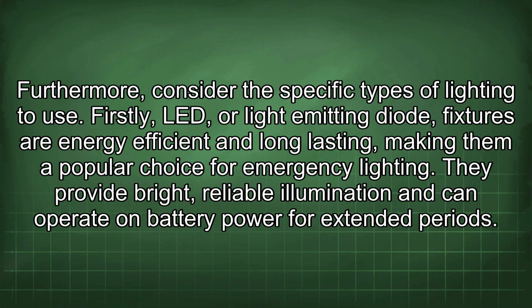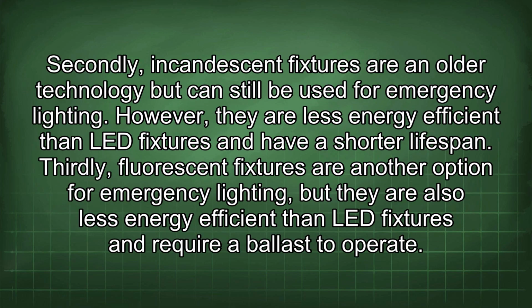Furthermore, consider the specific types of lighting to use. Firstly, LED, or light-emitting diode, fixtures are energy efficient and long-lasting, making them a popular choice for emergency lighting. They provide bright, reliable illumination and can operate on battery power for extended periods. Secondly, incandescent fixtures are an older technology but can still be used for emergency lighting. However, they are less energy efficient than LED fixtures and have a shorter lifespan. Thirdly, fluorescent fixtures are another option for emergency lighting, but they are also less energy efficient than LED fixtures and require a ballast to operate.